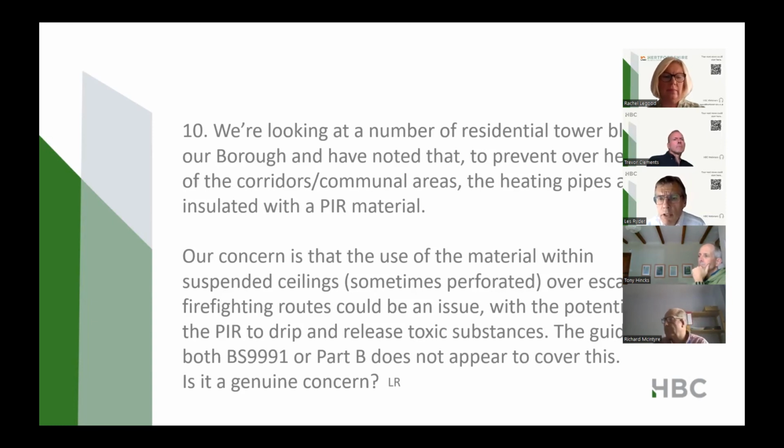We've got two fire safety renovations of existing tower blocks. Stevenage has sprinkled all of the towers, and Harlow have increased their smoke ventilation, made the smoke ventilation better. Now, neither of them fully comply with the 18-meter rule. Neither of them do so. So when you've got an existing tower block, then everything's a risk. If you haven't got full compliance, if you haven't got them all sprinkled and the smoke control isn't perfect, then I can understand why you would think that it's a risk with the insulation.